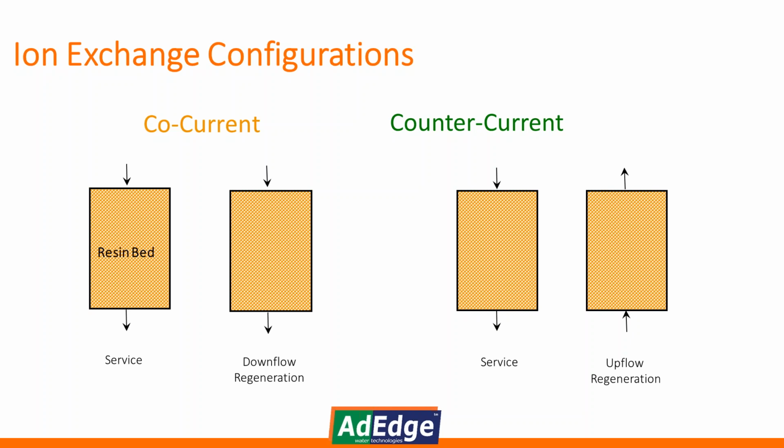And doing the upflow type regeneration, you then minimize leakage of nitrate that comes out of the resin bed. So you get a little bit more consistent nitrate level coming out of an ion exchange unit. One of the challenges with ion exchange and blending is you will see a variable nitrate level coming out of it. Say after a regeneration cycle, you might end up at say 2 to 3 milligrams of nitrate.